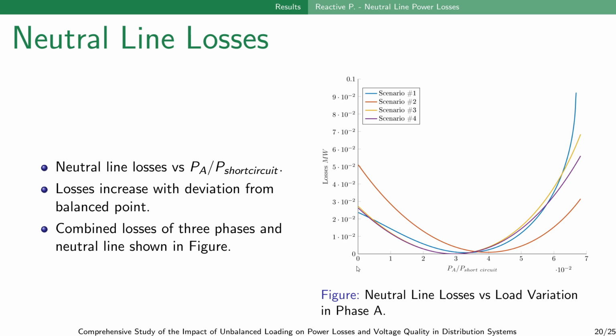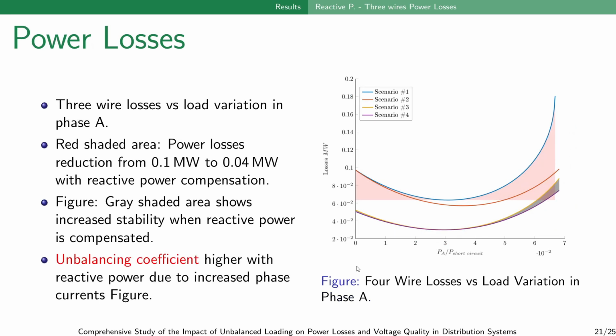This figure shows the neutral line losses against the phase A power ratio. As expected, losses increase with deviation from the balanced point. The combined losses of the three phases and the neutral line are also shown. This figure illustrates the power losses for the three phases against the phase A power ratio. The red shaded area indicates a significant reduction in power losses with reactive power compensation.